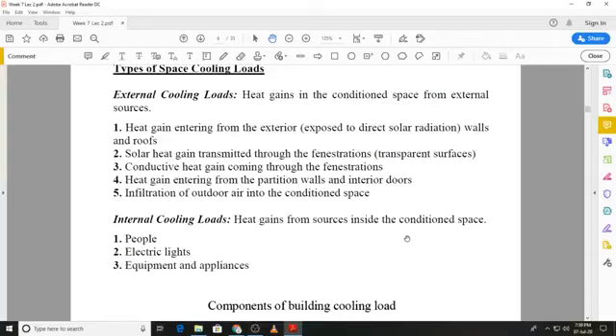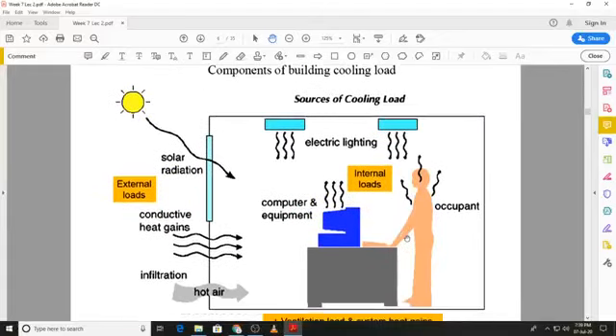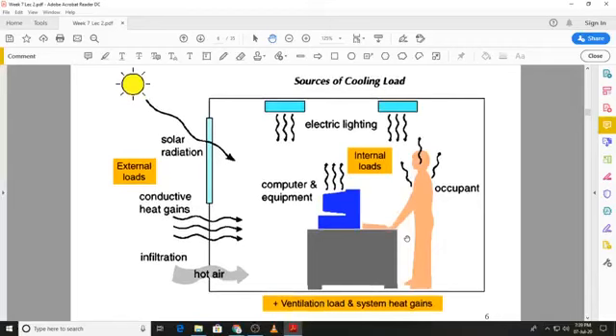these loads are pictorially shown to us as well, and you can see over here the various loads that we had talked about. And if we just look at the bottom, there is an additional mention of another load, that is ventilation load. When we say system heat gains, we are talking about the space cooling load, or the heat gain into the conditioned space. You have the exterior loads from an exposed roof or exposed wall, fenestrations, conduction that is through the walls and windows, transmission through windows, and conduction through the roof, infiltration. And inside we have the three sources of load: the occupancy, electrical lighting, and equipment and appliances.